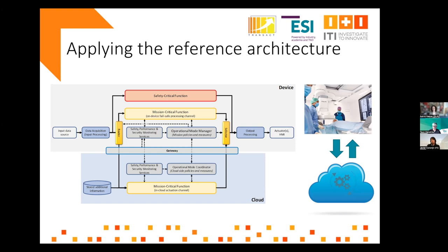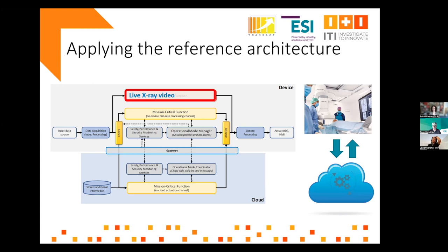Here is how we apply the reference architecture and figure out scenarios in which to apply it. We have drawn it from the input data to the output data. In the reference architecture, on the device we have the safety-critical function — in this case, the live x-ray video that must always be there, otherwise the surgeon cannot understand what he or she is doing. For the mission-critical functionality — the 3D reconstruction — in principle you want to do that in the cloud to have access to the latest and greatest algorithms with the most precision.